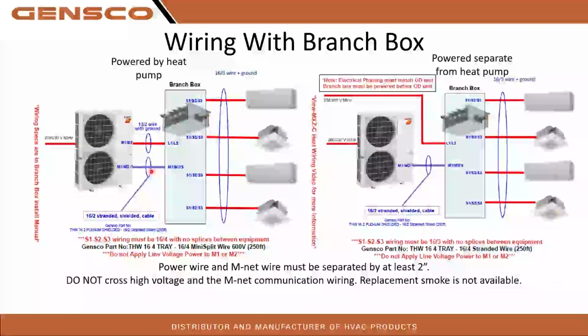Another thing that needs to happen is this power wire and this communication MNet wire need to be separated by at least 2 inches. What ends up happening is your high voltage AC here does put off an electromagnetic field that can screw with your communication on our MNet. So at least 2 inches apart.